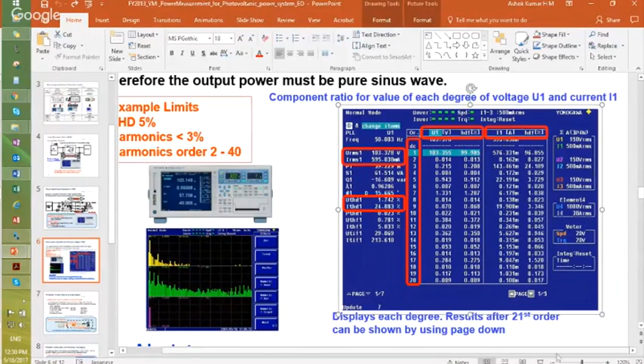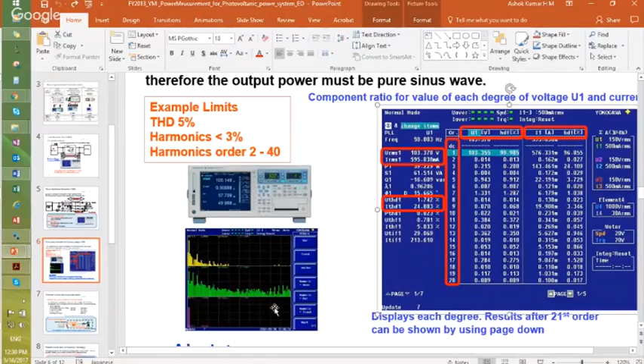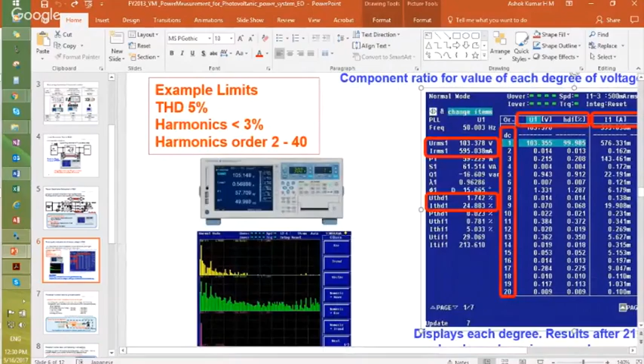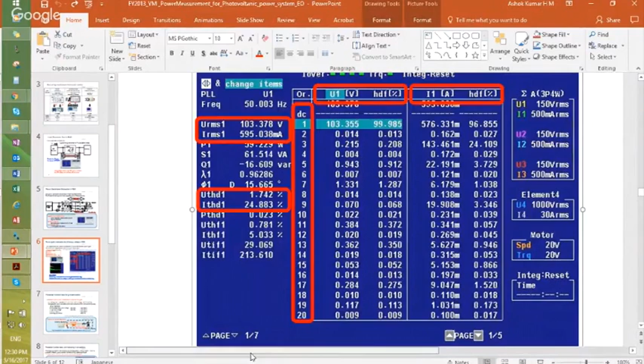So this is in the numerical format, and if you come to the graphical or bar graph format, you can see here, this is the bar graph. Yellow color is the voltage harmonics, and we have seen the voltage 7th harmonic is the highest, and the current 3rd harmonic is the highest. Similarly, we can see the bars in the 3rd and 7th harmonics on the highest side. The bottom one is the power harmonic.